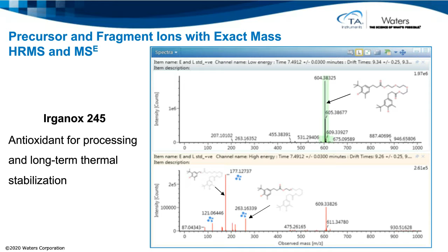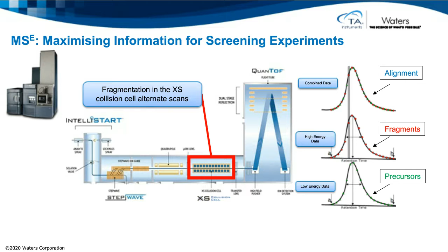Here is the schematic of the Waters Xevo G2-XS QTof. The XS collision cell, which is highlighted in red in the middle of the schematic, is what lends us the capability to run MS^E. Alternating low collision and high collision energy is applied, enabling the simultaneous acquisition of precursor and fragment ions throughout the entire chromatographic run. Later, during the data processing, precursor and fragment ions will be precisely aligned based on their retention time. So for every peak, we will have the exact mass of the compound and its corresponding fragments. And as I said, this information helps when we're screening and in structural elucidation of compounds.